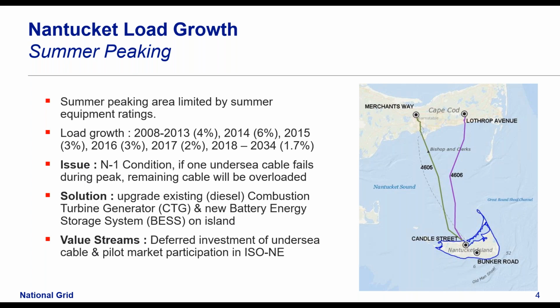The issue we were solving was an N-1 condition: as shown in the photo, there are 2 cables to the island, and if one undersea cable fails during peak, the remaining cable would become overloaded. The ultimate solution we chose was upgrading the existing diesel combustion turbine generator and installing a new battery energy storage system in combination. This deferred the investment of additional undersea cables and allowed us to pilot market participation in ISO New England.